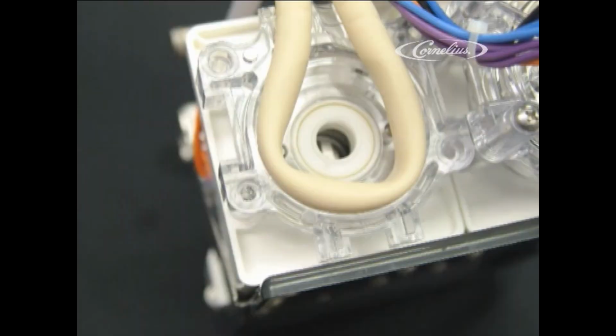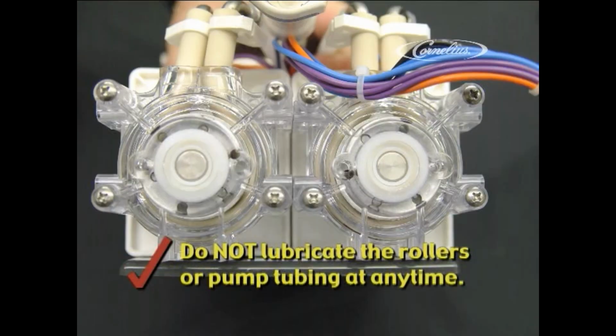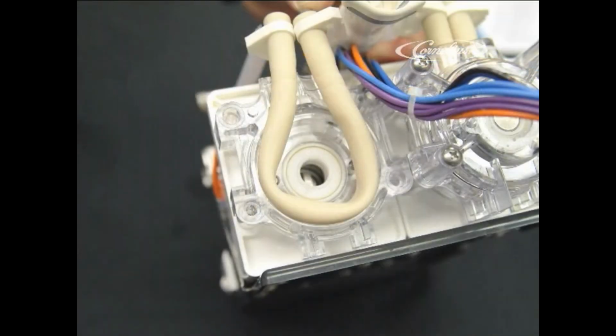Another indication is if you find rubber shavings in the bottom of the pump halves. This indicates a binding roller. Do not lubricate the rollers or the pump tubing at any time. The pump tubing is a peroxide impregnated silicone tube that will stand up to 3 million cycles before it needs replacement.